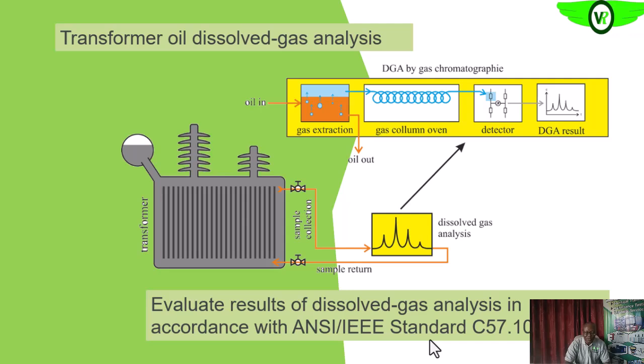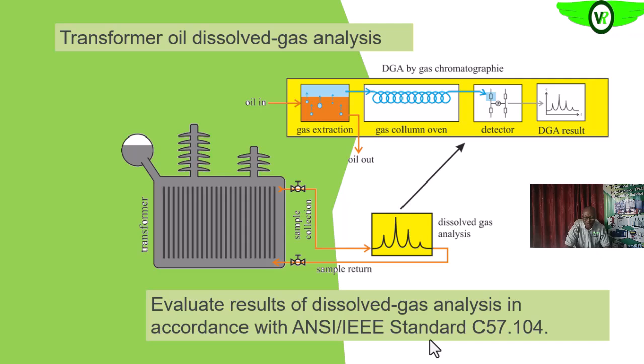So we can also test the transformer oil for dissolved gases. Those dissolved gases, after analysis, will tell us much about what is happening within the oil. So carry out that dissolved gas analysis to ascertain the integrity of our transformer.